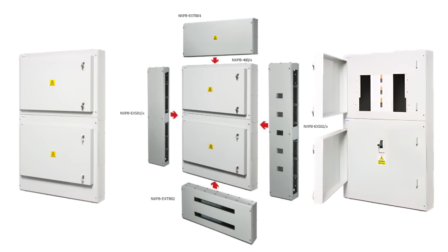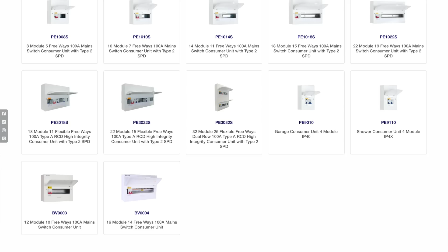Deta Electrical has announced that it's extended its Protect Plus range with consumer units designed to support air source heat pumps. The boards incorporate Type B RCDs and Type B HP RCDs suitable for heat pumps. The latter require enhanced characteristics of 20 kHz or greater with a minimum tripping point of 150 mA above 1 kHz. Devices include bidirectional switched neutral RCBOs, RCDs, MCBs and AFDD RCBOs. All enclosures are pre-fitted with Type 2 surge protection devices and boast lockable visors and floating bus bars.